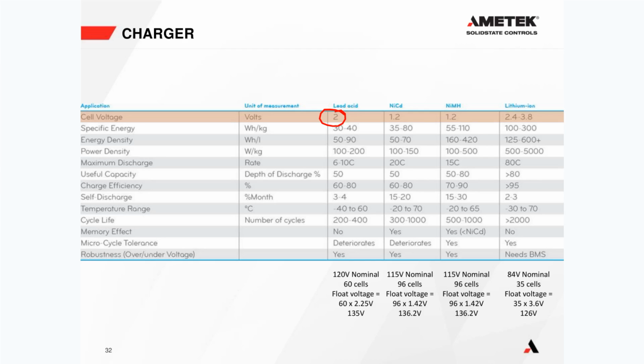The reason why the charge voltage is higher is that's the voltage you need to maintain the charge in the cell with a minimum amount of power and losses. The battery manufacturer works out all of its chemistry, does all of its testing. It says, okay, we have figured out that for our lead acid cell, if you charge it at 2.25 volts per cell at 77 degrees, you're going to get the best lifespan out of it, and it's going to maintain its charge. It's a very fine line. So that is why the float voltage is actually greater than the cell voltage. And that's the same for NiCads.